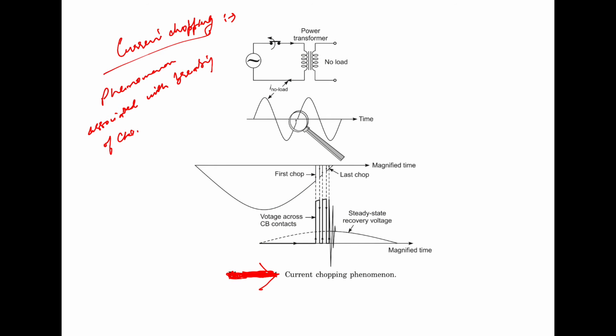Now we can discuss the phenomena associated with the breaking of the circuit. When the circuit breaker tries to switch out an element of the power system, it encounters certain phenomena peculiar to the element being switched. For example, when an unloaded transformer is switched off, the phenomenon of current chopping may be encountered. Whereas when a capacitor is being switched off, there may be a tendency of the voltage across the circuit breaker to rise in a stepped fashion.